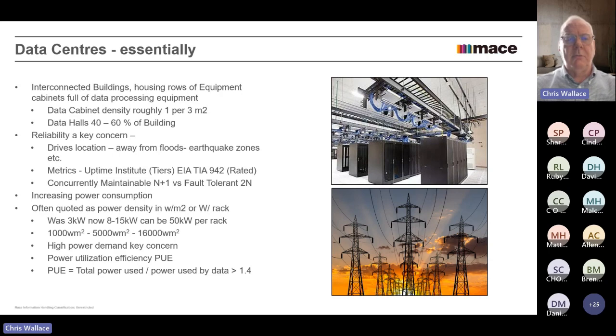One of the metrics when we look at how reliable a data center is, there are two basic metrics that the industry uses. One is the Uptime Institute, uptime being the opposite of downtime. And the other is the EIA, TIA 942. Uptime Institute a while ago started off as really like a boys club of data center owners and operators, sharing information freely as to what they could do to make sure that their data center was up and not down. They came up quite quickly with a concept they called tiers. Then eventually they commercialized it and monetized it, and now the word tiers is actually trademarked. So EIA, TIA, who have done a very similar thing, in early days cooperated with Uptime Institute. They can't use the term tiers anymore. They've got to call it rated. So I'll use the word tiers for want of a better, but rated is almost the same.